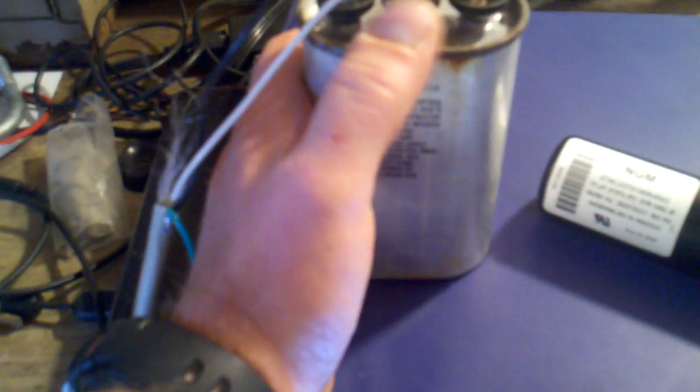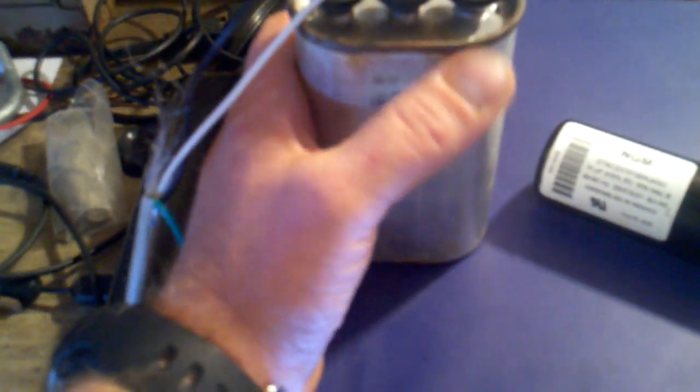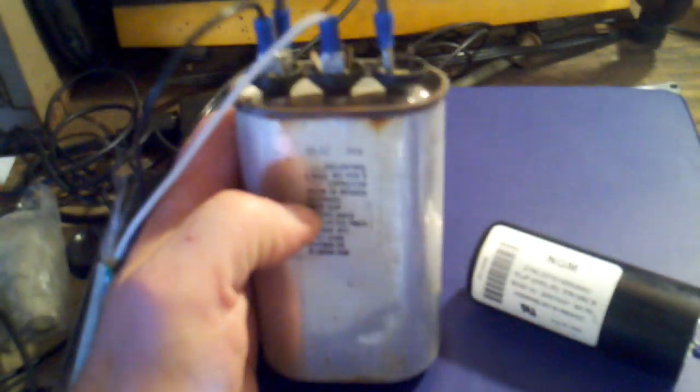You have a common and then you have a fan and a herm. These are set up for central air conditioning units where it has a fan and a compressor in it. Your common would connect here. This is a 35/5 - a 35 microfarad and a 5 microfarad.